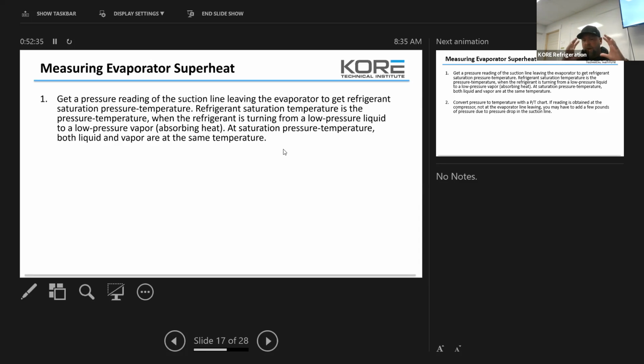So that's why evaporator superheat matters for the efficiency of the case. Compressor superheat matters for the life of the compressor, to sustain that compressor. Because if you go to any compressor class, they're going to tell you the one thing that keeps compressors alive is cool gas.